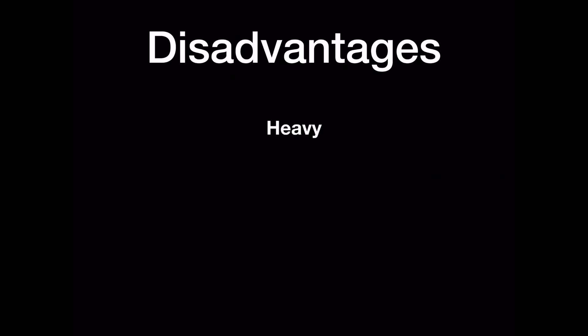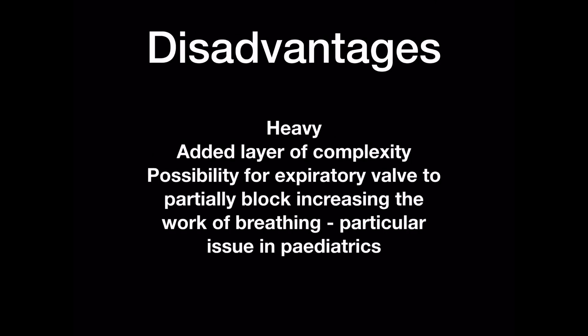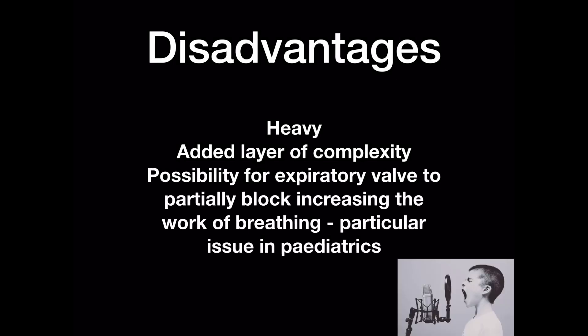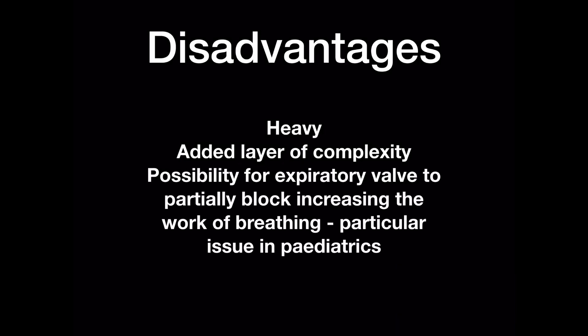Disadvantages: It appears to be more of a historical system in UK human practice. It is heavy and arguably complex to use, requiring training. The presence of an expiratory valve is a potential disadvantage in paediatrics, as this may increase resistance in the circuit, increase the work of breathing, and there is also potential for the valve to malfunction.